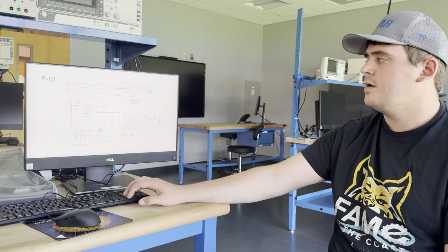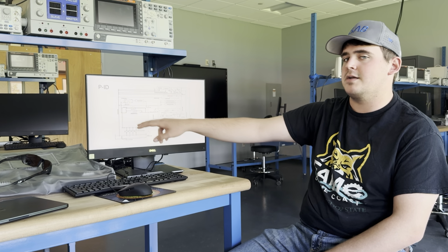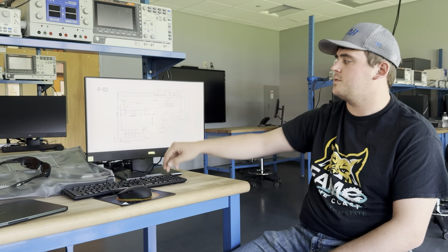This is a P&ID, so there are 4 700 horsepower low pressure centrifugal pumps, 2 high pressure pumps, and then 2 temper loop pumps. So these drive it to the process cooling loop and the process low pressure and high pressure loop, and then the rest of it goes through the temper system and through the blowdown water, and then it all falls into this warm water basin where it is then pumped back into the main tank. The water in the main tank is constantly being recirculated through the 2 chiller pumps to keep it under 82 degrees.